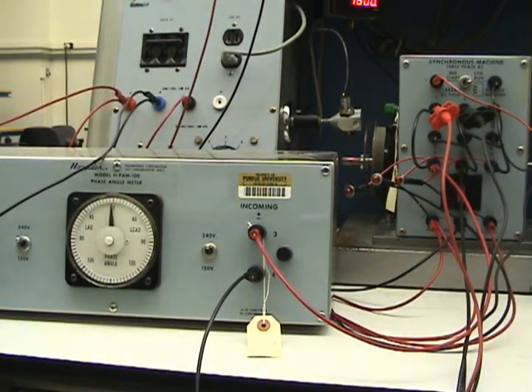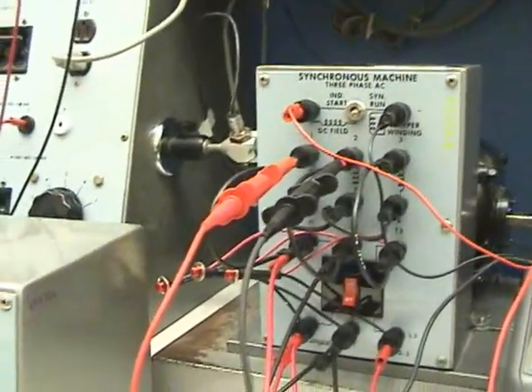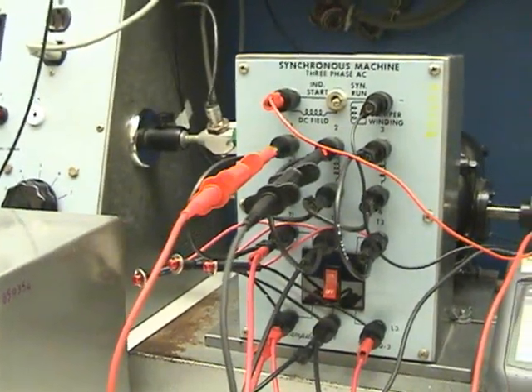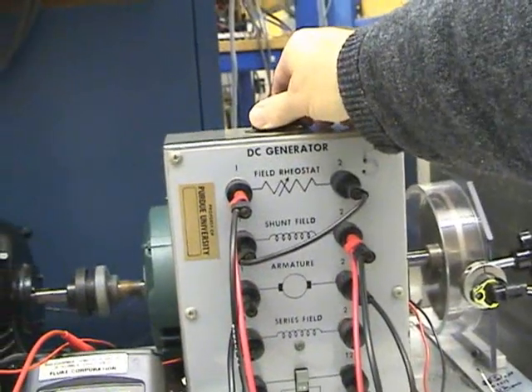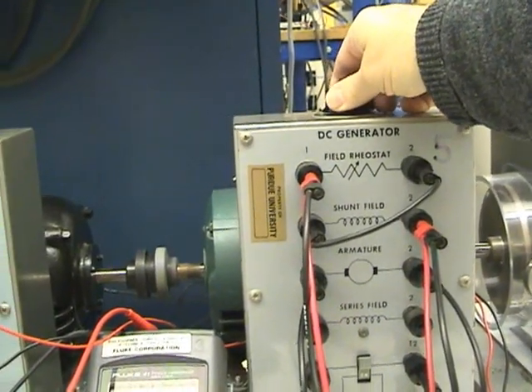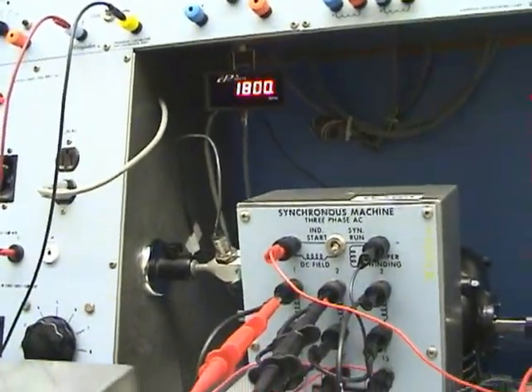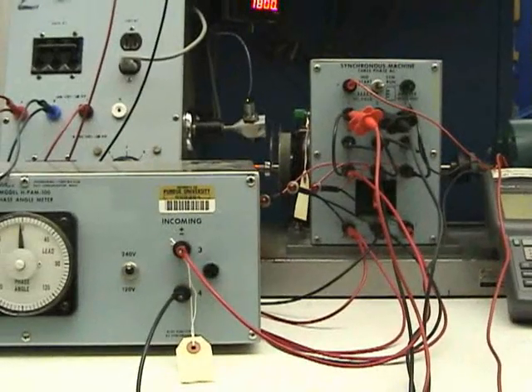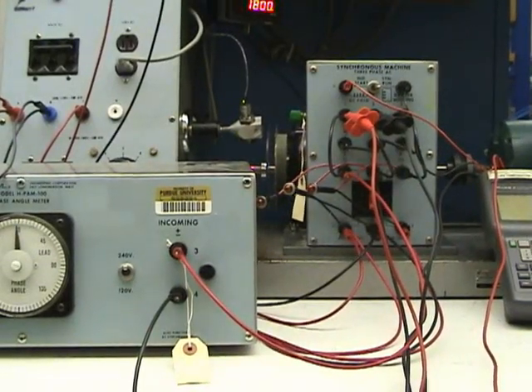And so as it comes up to zero, I've hit the switch, locked it in. Now the machine is running in synchronism, and I can do anything I want to the machine essentially, and it's not going to change speed. And so if I adjust, for example, the rheostat here, it has no effect on the speed of the machine. It stays right at 1800 RPM. So this is the proper procedure for synchronizing your machine, and you'll be doing this in the laboratory experiment today.